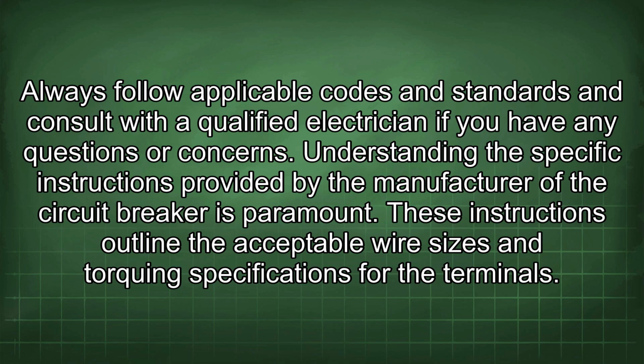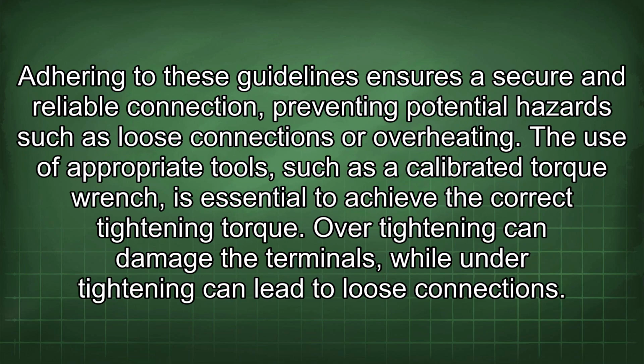Understanding the specific instructions provided by the manufacturer of the circuit breaker is paramount. These instructions outline the acceptable wire sizes and torquing specifications for the terminals. Adhering to these guidelines ensures a secure and reliable connection, preventing potential hazards such as loose connections or overheating. The use of appropriate tools, such as a calibrated torque wrench, is essential to achieve the correct tightening torque. Over-tightening can damage the terminals, while under-tightening can lead to loose connections.